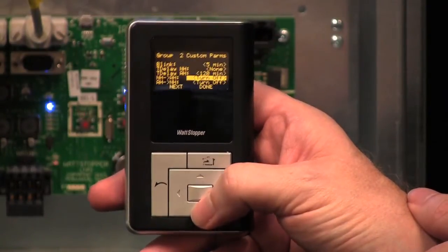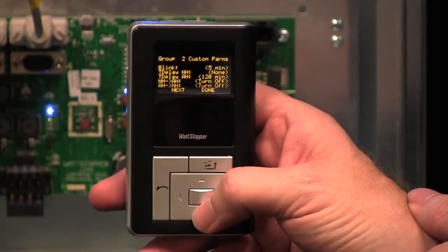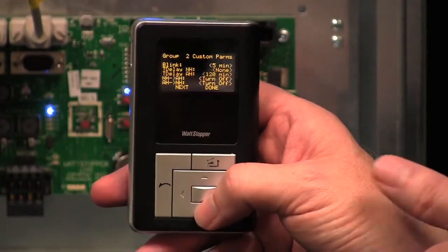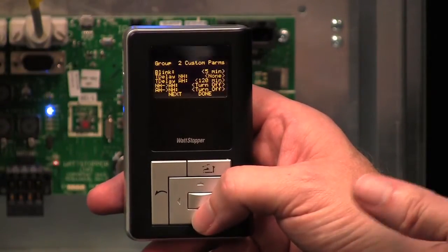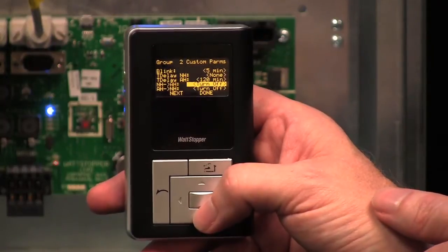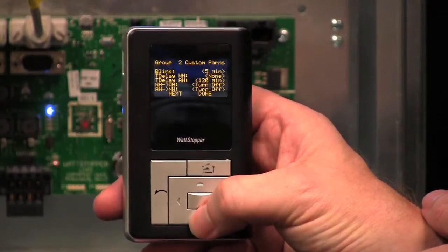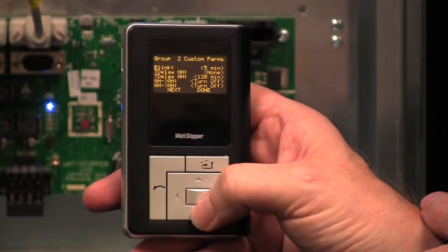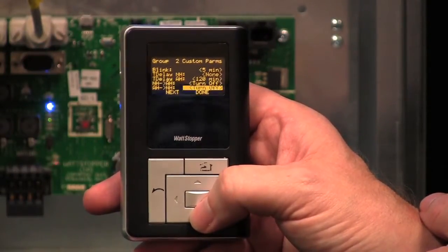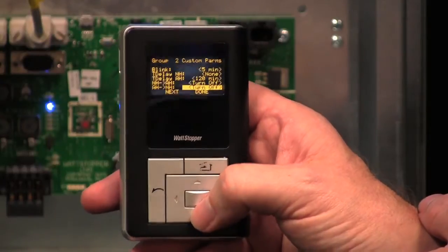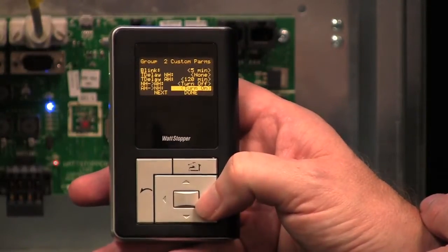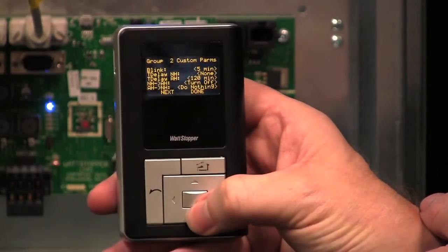And then the next 2 things it's going to ask are, what do we want to have happen when the panel goes from normal hours to after hours? Now think about that. That's typically going to happen in the evening time. What do we want to have happen? We want the lights to turn off. We'll leave it as that. For after hours to normal, so this is typically in the morning, what do we want to have happen? We're going to say do nothing.